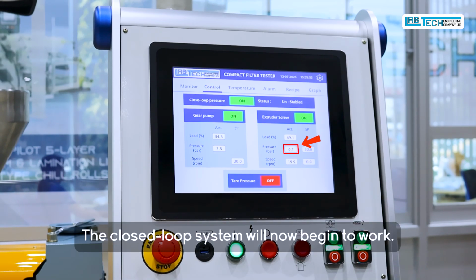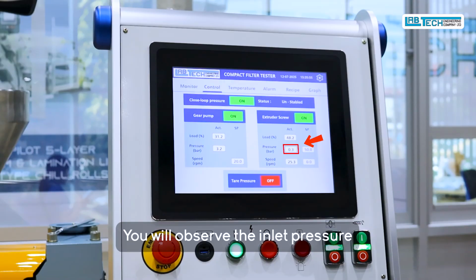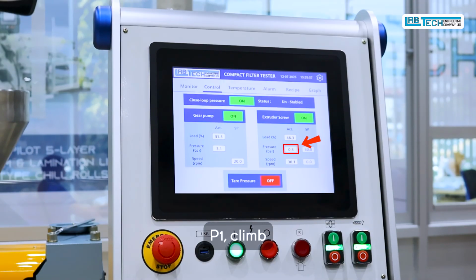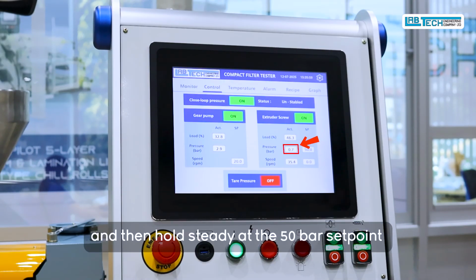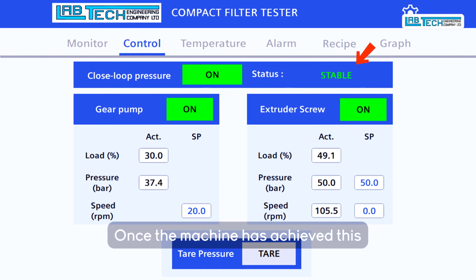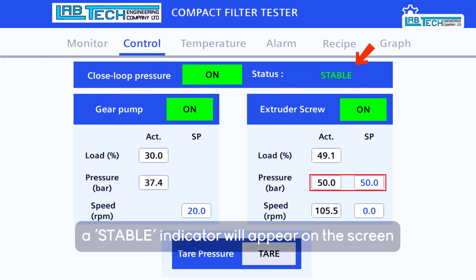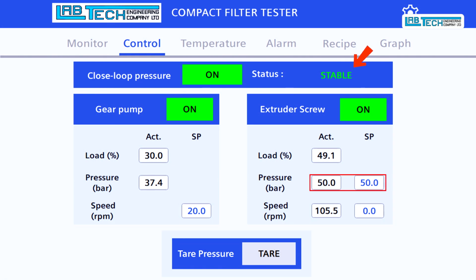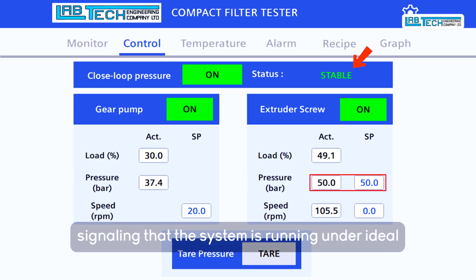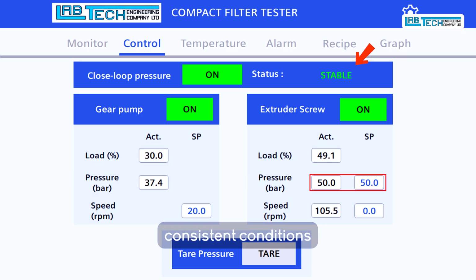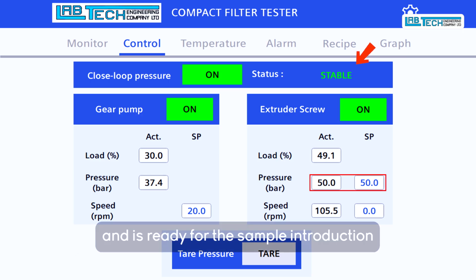The closed loop system will now begin to work. You will observe the inlet pressure, P1, climb, and then hold steady at the 50 bar set point. Once the machine has achieved this, a stable indicator will appear on the screen, signaling that the system is running under ideal, consistent conditions, and is ready for the sample introduction.